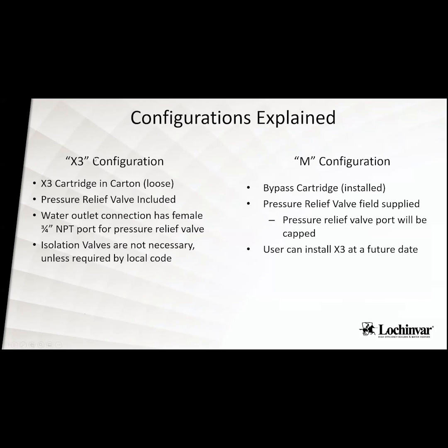So as I said before, the X3 configuration comes with the X3 cartridge loose in the box. It also comes with that 3/4 NPT pressure valve that's in there, and isolation valves, again, are not necessary on that. If you buy it in the M configuration, which is non-filtration, you would need to field supply that pressure relief valve and the isolation valves. You can add an X3 cartridge later on if they wanted to, but that heat exchanger is still going to have water quality requirements if you buy it as the M. If you buy it as the X3, it does not have any water requirements. Does that make sense? Makes sense. Okay.